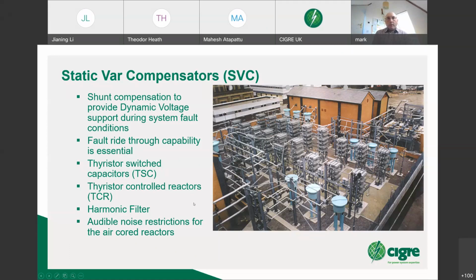One of the things typically associated with the static VAR compensator are harmonics, and harmonic filters tend to be quite a feature associated with SVCs, since wherever you are connecting something, you need to make the background harmonics no worse than they were. Obviously harmonics are generated by a whole variety of other things, but we typically aim not to aggravate any existing condition, and filters are the method by which this is done. Wherever we have a thyristor controlled reactor, that's a key part of the design.